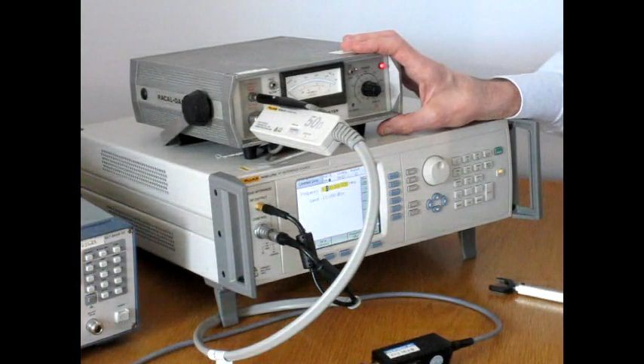This RF millivoltmeter is specified to operate from a frequency of 10 kHz up to and above 1 GHz. So we're going to have a look at the frequency response relative to the frequency of 10 kHz. So first of all we will set a frequency of 10 kHz on the 9640, and we're going to calibrate the 100 millivolt range of the RF millivoltmeter. So I'm going to set my 9640 level in terms of millivolts. So I'm going to use the units facility to change into volts RMS and then select 100 millivolts.